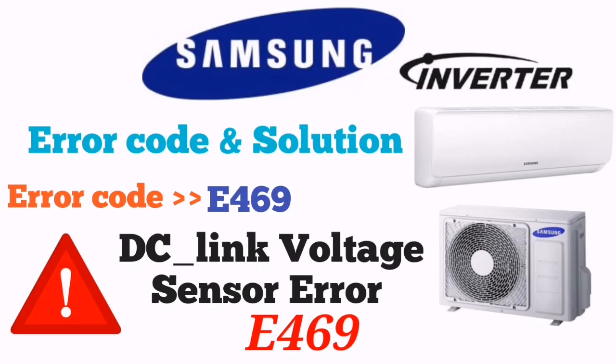And if you are not getting this voltage, then you have to exchange your outdoor PCB. And if you exchange the PCB and it is still not working, then you have to check the insulation of your reactor. If the reactor insulation is not good, then you have to change the reactor and your unit will be in working condition.